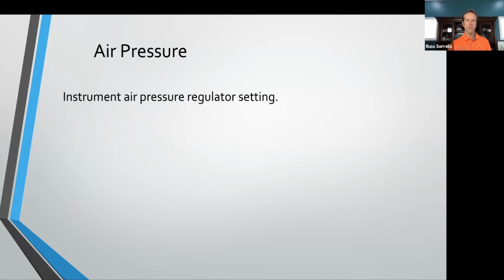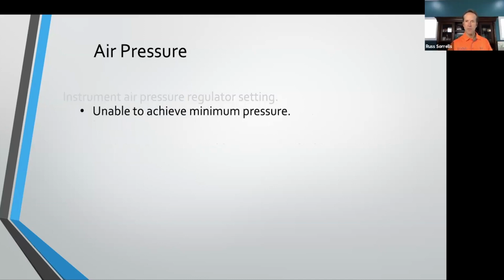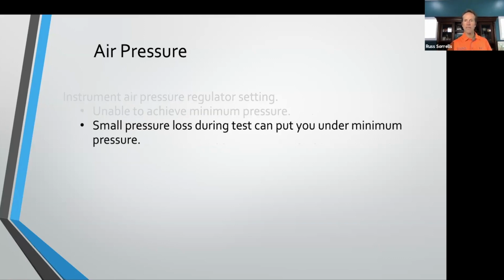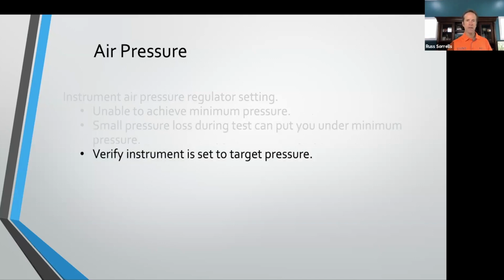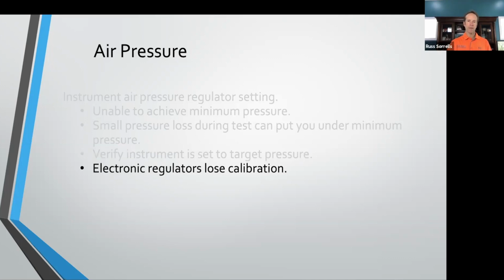All right, very good. So instrument air pressure regulator settings, we mentioned that. You're unable to achieve minimum pressure. A small pressure loss during test can put you under the minimum pressure. I mentioned that earlier. You want to verify that the instrument is set to the target pressure. This is a common challenge that we have. In our instrumentation, you tell it what test pressure you are going to be operating at. And if you tell it 60, but you set it up to 50, obviously that's going to be a problem. Sometimes if you're using an electronic regulator, they can lose calibration, and that has been an issue that I've experienced a time or three.